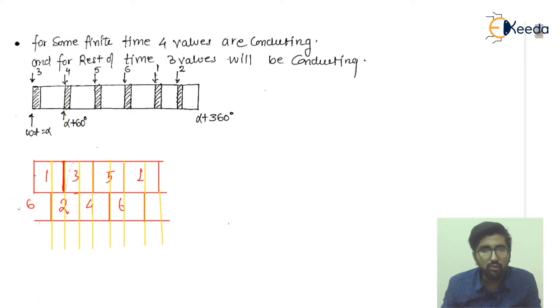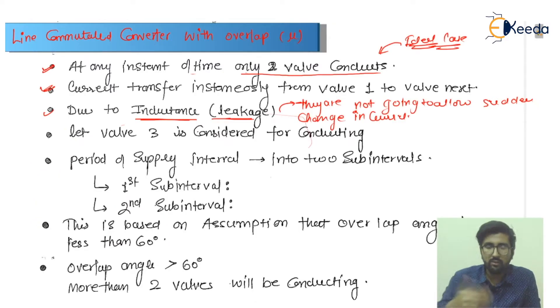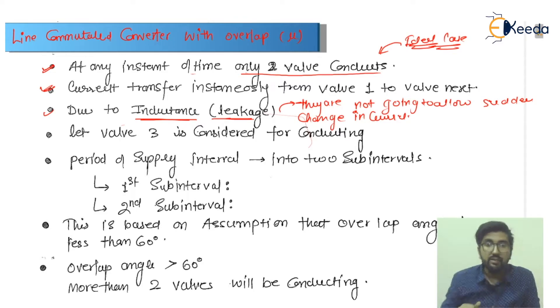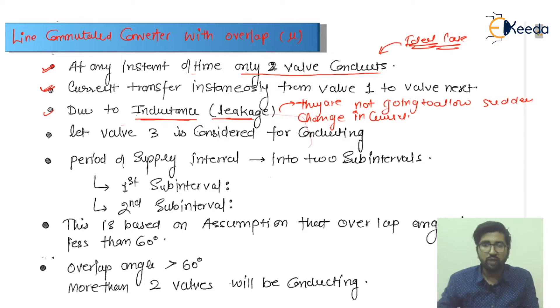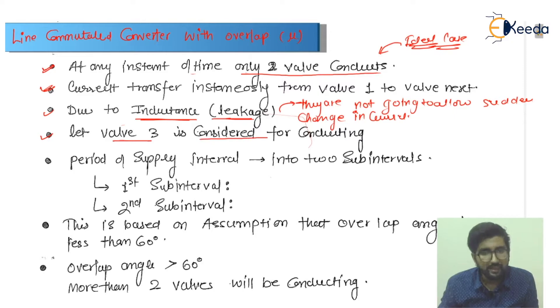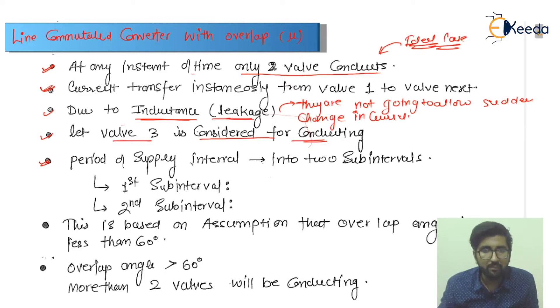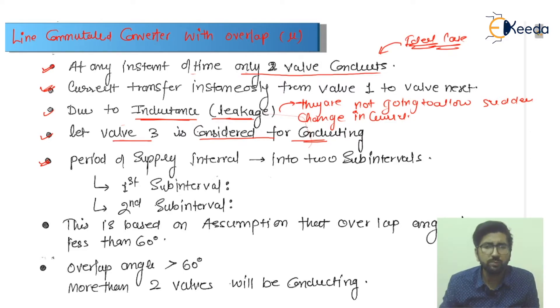The period of time during which valve one and valve three are both conducting simultaneously is called the overlap angle. During this interval, we can divide the supply interval into two sub-intervals: in the first sub-interval, three valves are conducting, and in the second sub-interval, two valves are conducting.